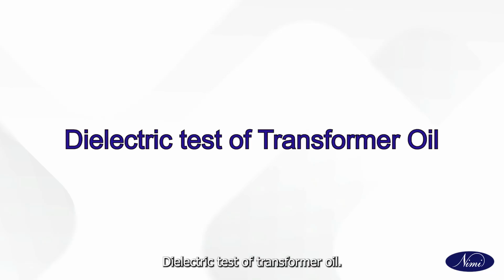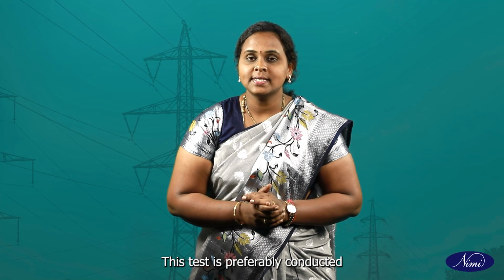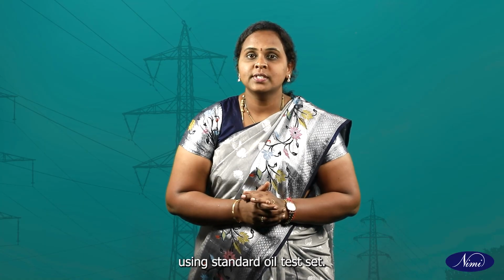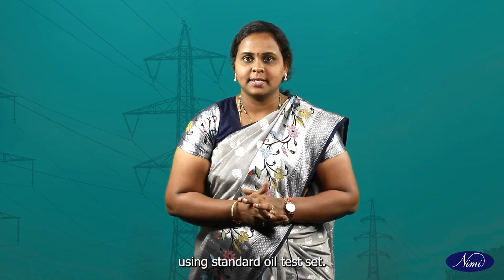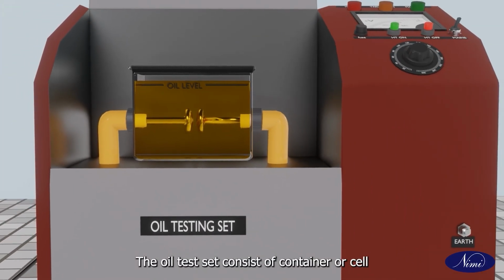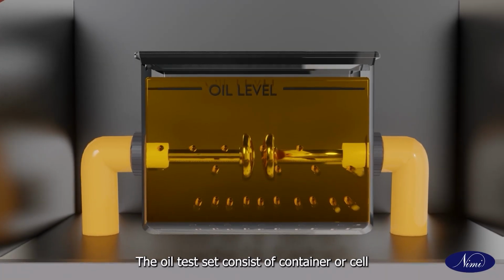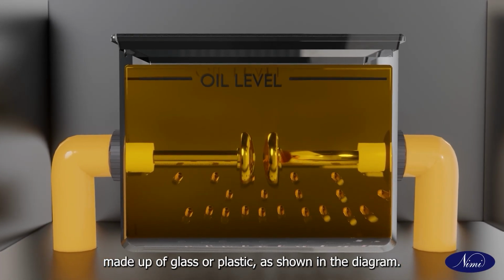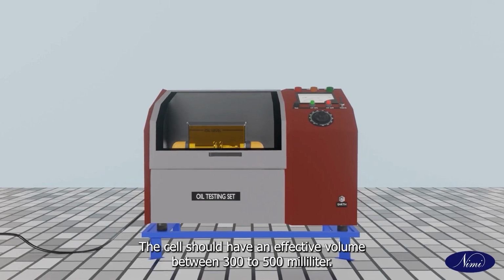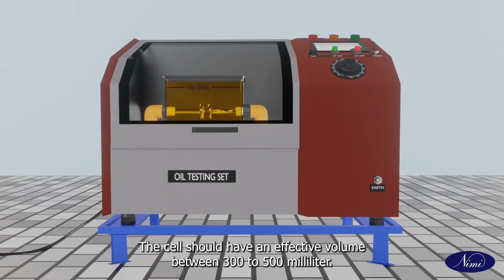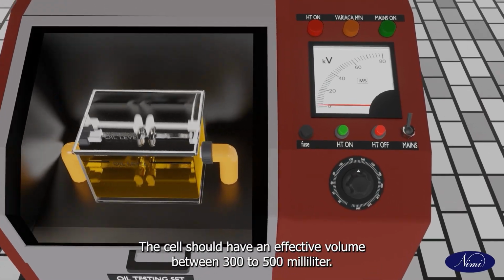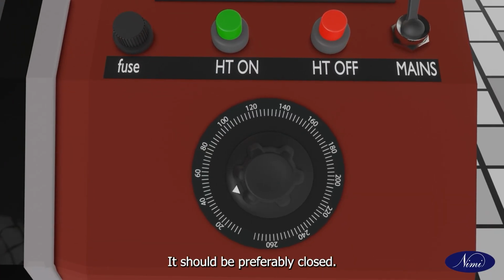Dielectric test of transformer oil. This test is preferably conducted using a standard oil test set. The oil test set consists of a container or cell made up of glass or plastic. The cell should have an effective volume between 300 to 500 milliliter. It should preferably be closed.